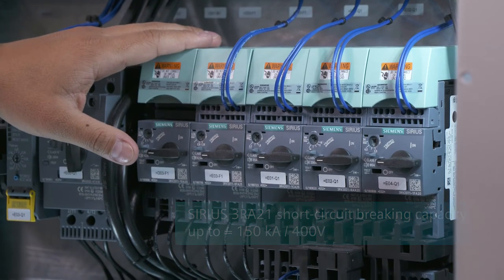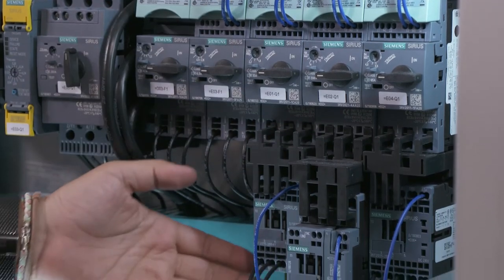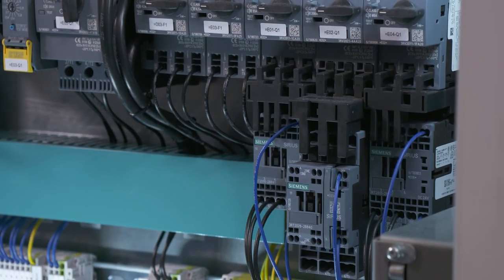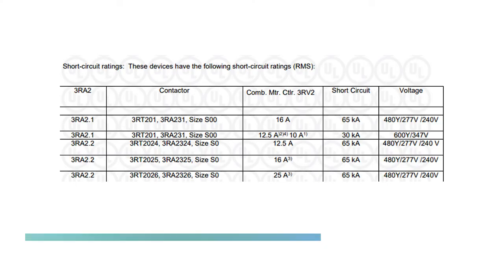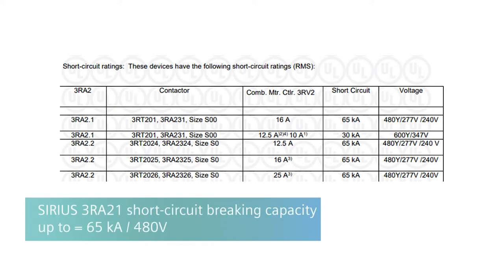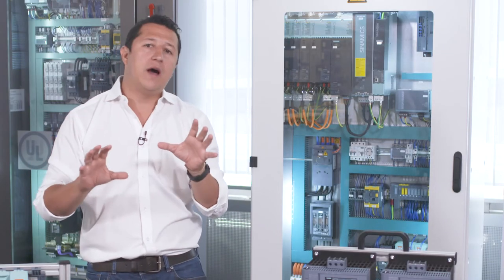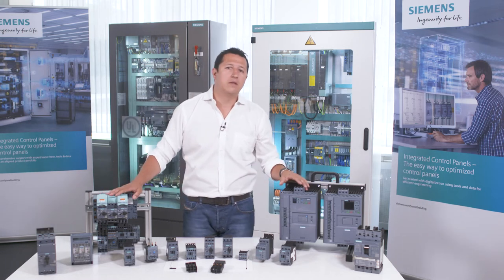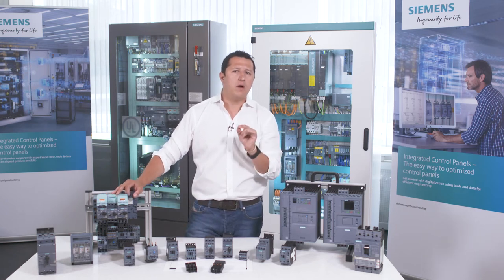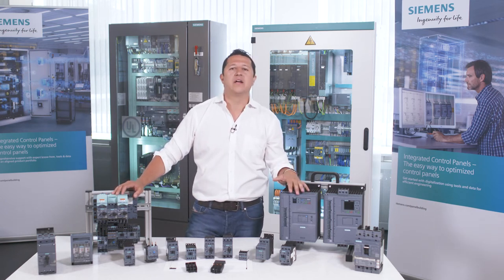These load feeders have also been tested according to North American UL and CSA standards, also as part of a tested combination. The values for the UL standard are 65kA at 480V. The goal is therefore the same — only the values differ depending on the standard requirements in various markets. We have a standardized solution for various markets, but keep in mind that SCCRs will vary according to the product standards that must be complied with at Siemens.